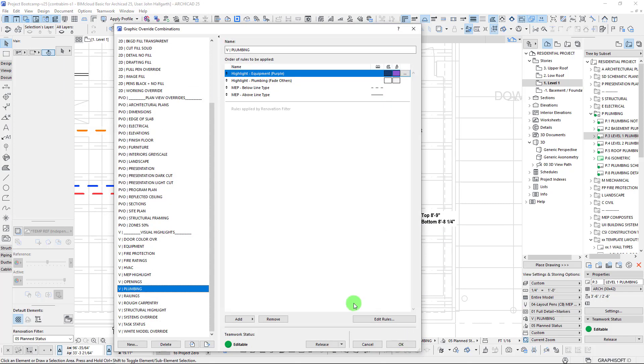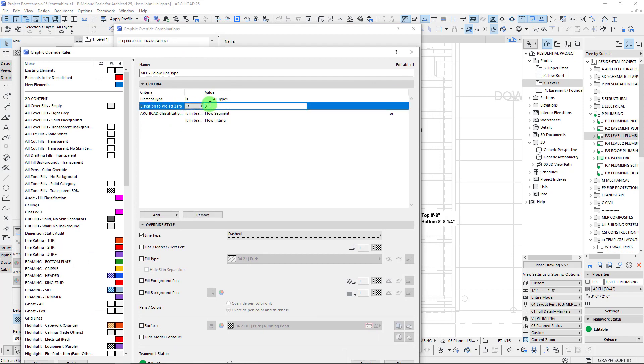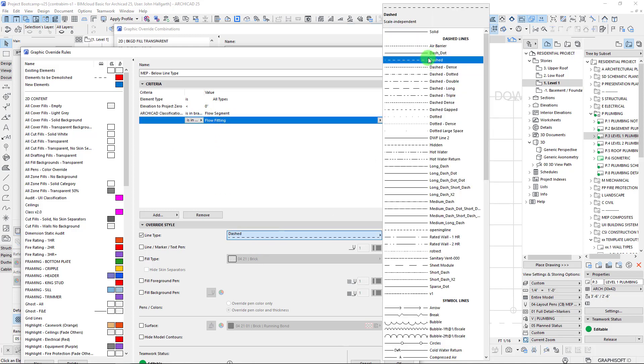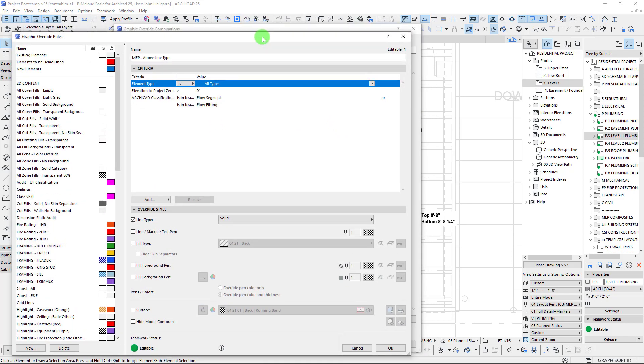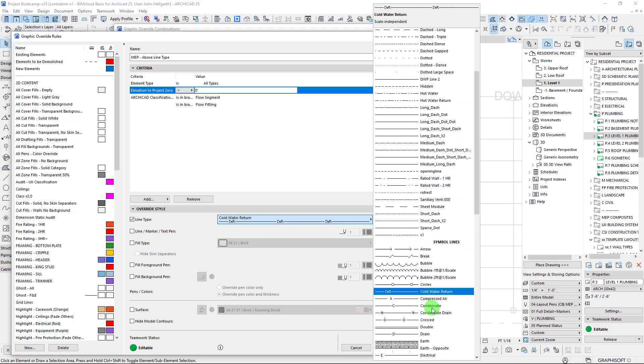In this graphic override we have two rules in play on top of our visual highlights. The first is our MEP below line type — it looks for all elements below zero that are in the branch of a flow segment or flow fitting, and overrides them with a specific dashed line. The above rule makes them solid through the exact same workflow. We could also create additional layers — say if we wanted to show stuff above eight or ten feet — by adding another filter using the elevation of the pipes themselves to determine the override.